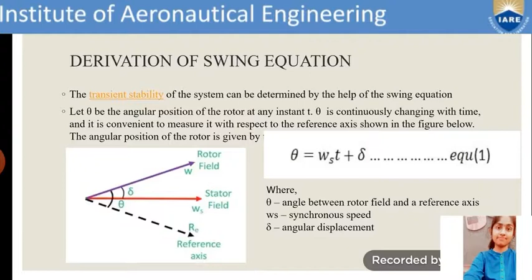Since generator terminals are assumed to be connected to the grid, the stator field axis can be taken as reference for the study of relative motion. Due to this relative motion, the load angle delta will vary with time. Let theta be the angular position of the rotor at any instant t. Theta is continuously changing with time, and it is convenient to measure it with respect to the reference axis shown in the figure below. The angular position of the rotor is given by theta equals omega s t plus delta. Theta is the angle between the rotor field and the reference axis. Omega s is the synchronous speed. Delta is the angular displacement. These parameters are taken from the observation of the generator, not the motor.